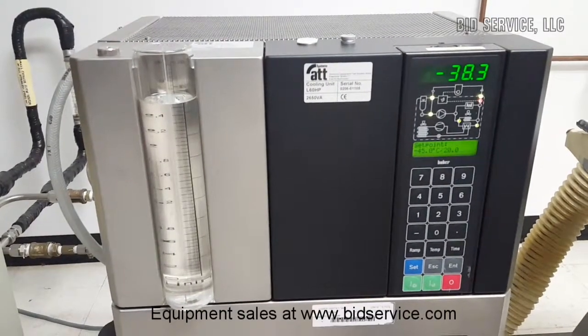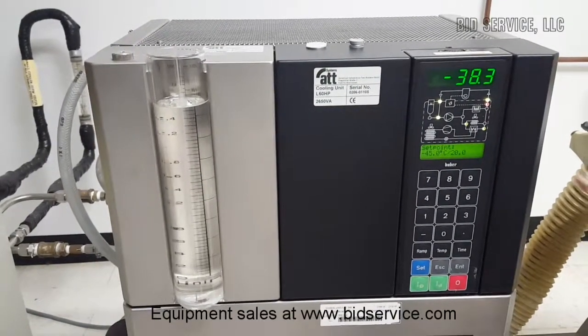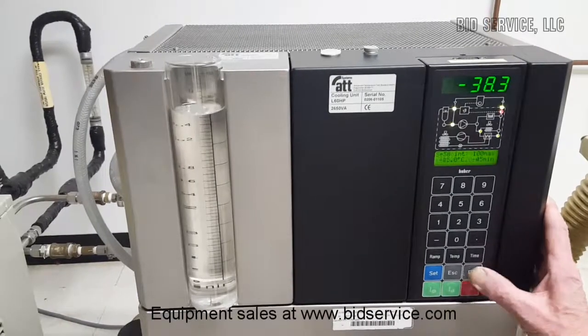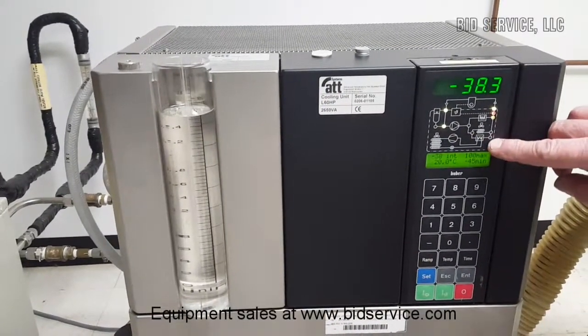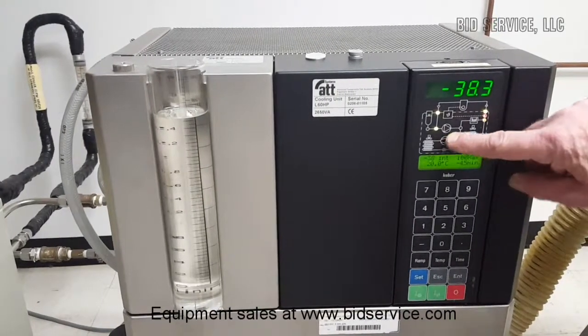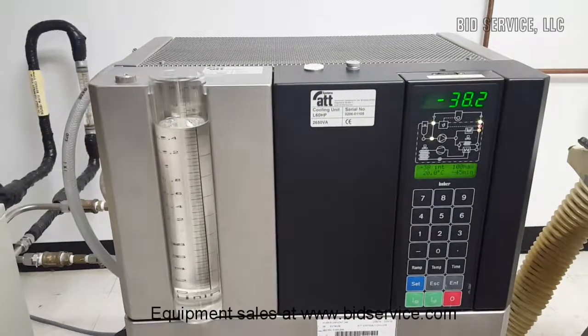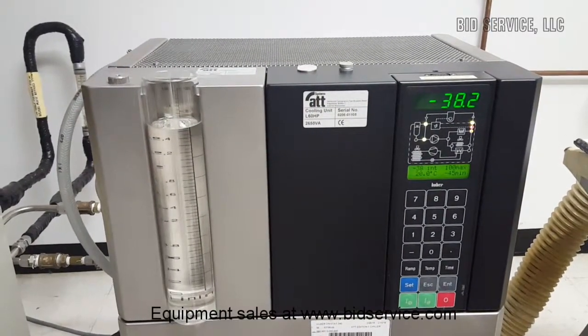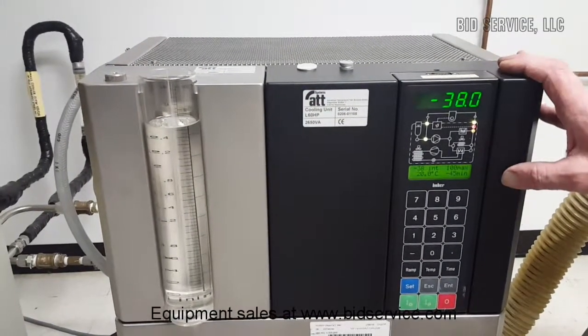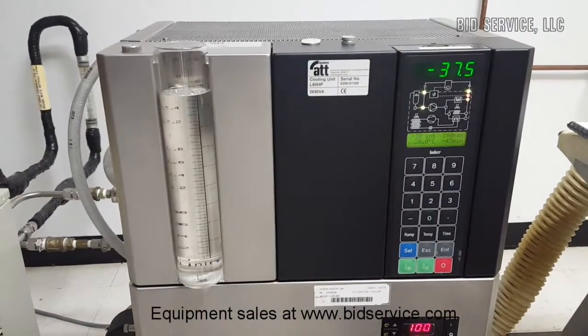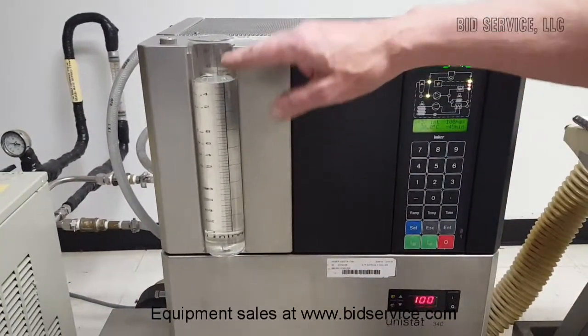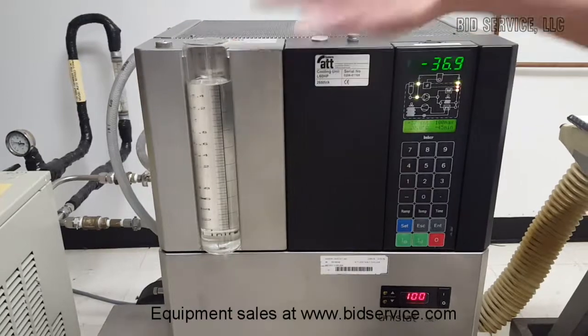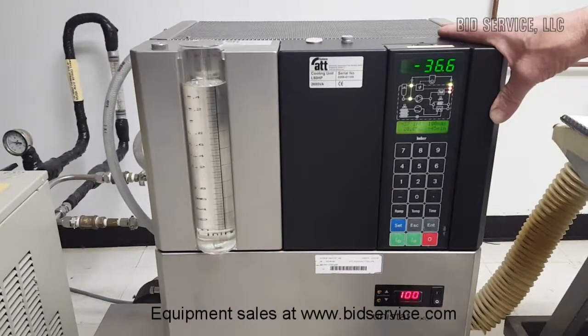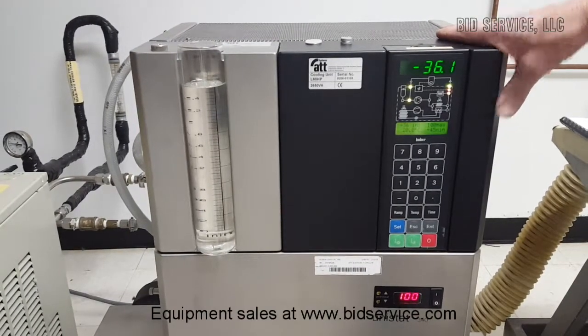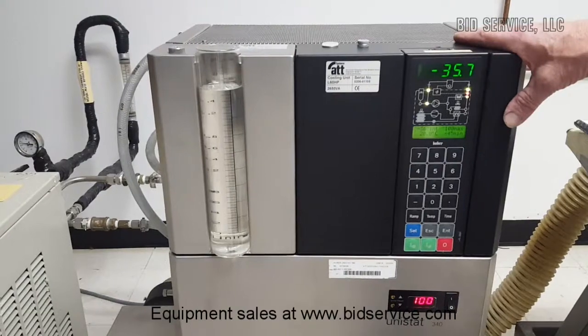And shortly the valves will shift and this will start heating up. Notice the refrigeration valves went off and now we will be heating up. As you can see, it is already starting to climb in temperature. There you go. So what I'm going to do now is get back to ambient temperature. Then I'm going to drain all the alcohol out of the system. And for our heat up part of our demonstration, I will just fill it with good, clean DI water. And we're going to heat it up to about 80 degrees C, which is 176 degrees Fahrenheit. Just to show you that it does heat up. And so we'll have you guys back in a little bit.